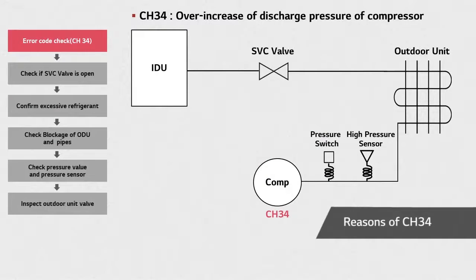Error CH34 is caused by an increase of discharge pressure. If the high pressure is increased, the compressor will be kept in off state. Some reasons for this error include closing of the service valve, excessive refrigerant, and blockage of the outdoor unit and piping.